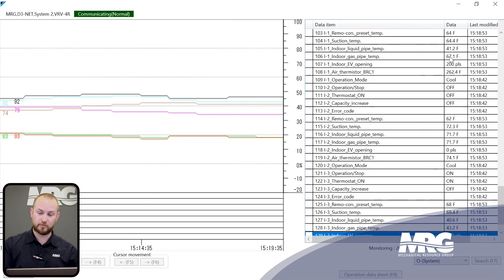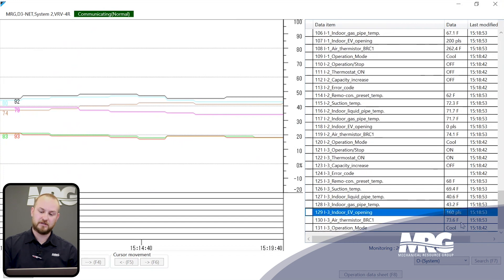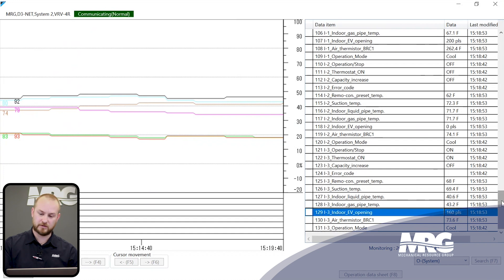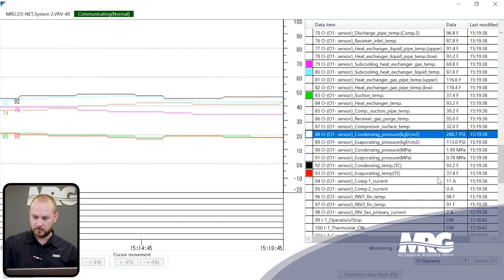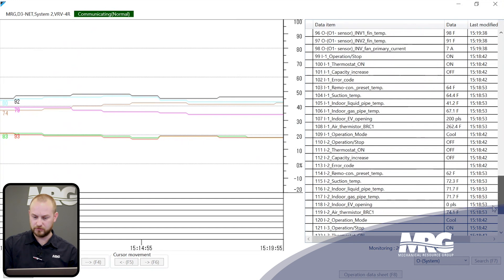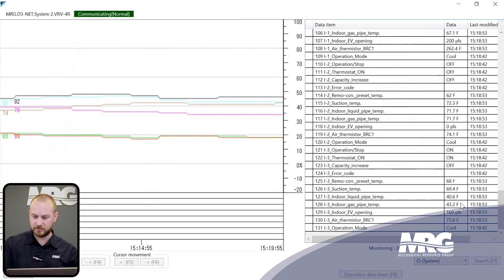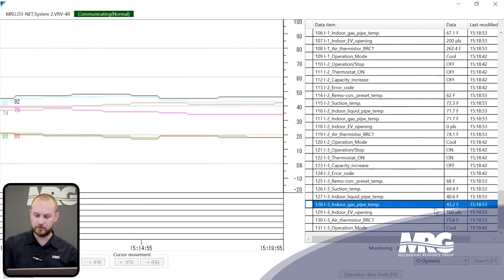The first unit is actually absorbing some heat while this one is not, which tells us this position is probably not accurate. Scrolling back up to evaporator temperature, we're pretty close to the temperatures measured at this indoor unit — and so there are a couple of things we'd want to immediately look at with this unit.